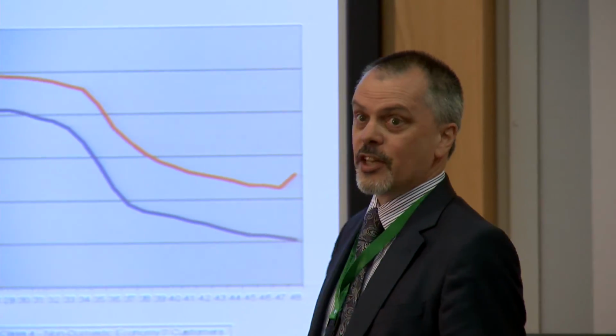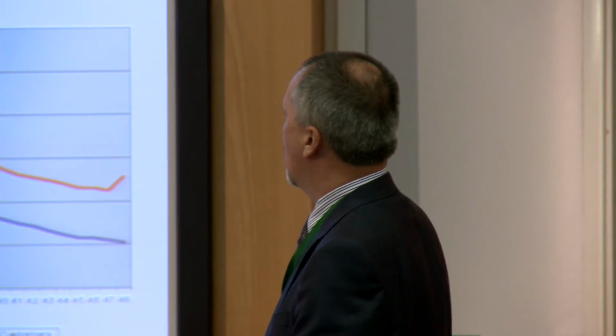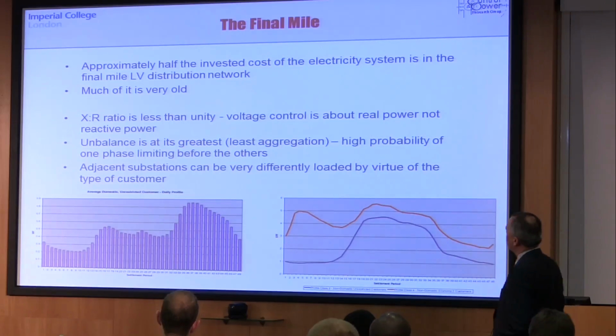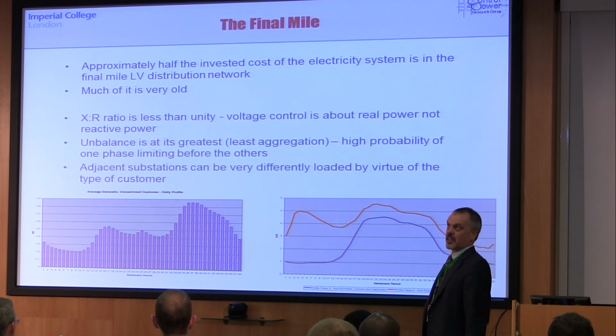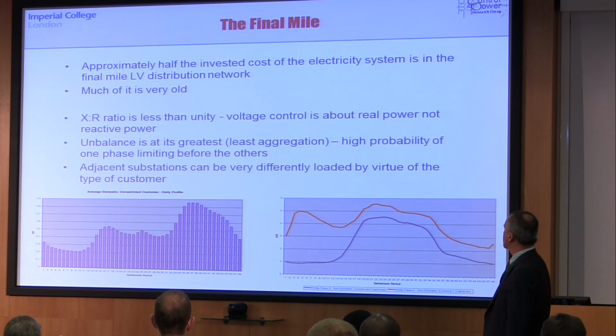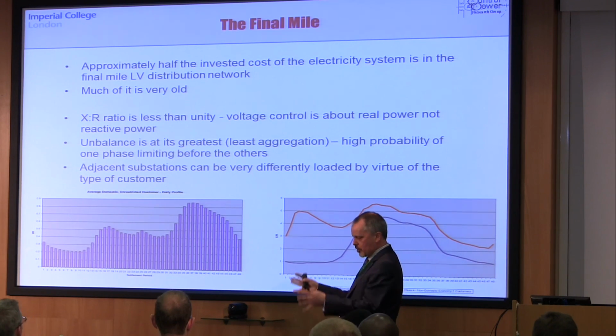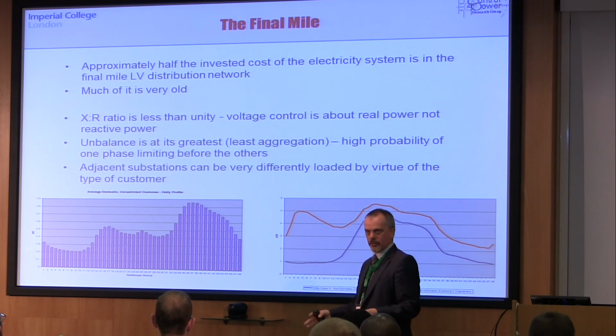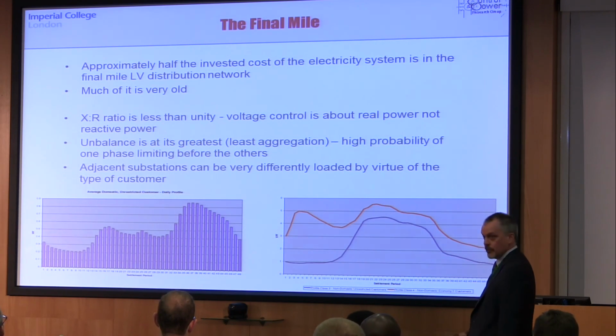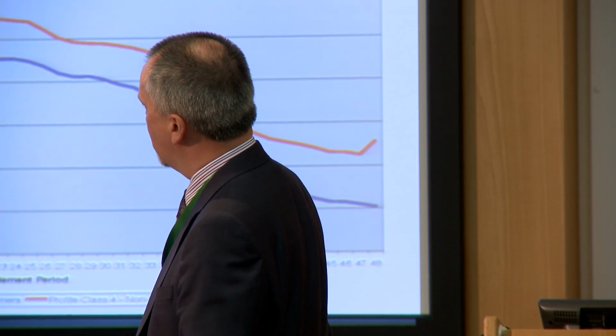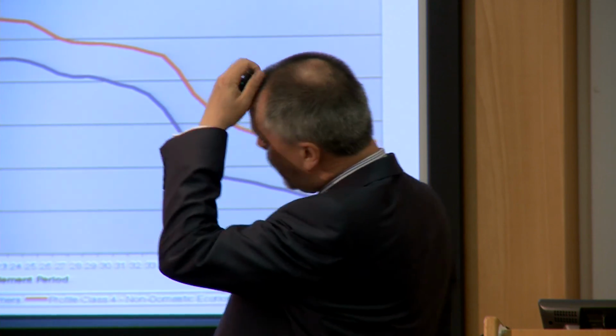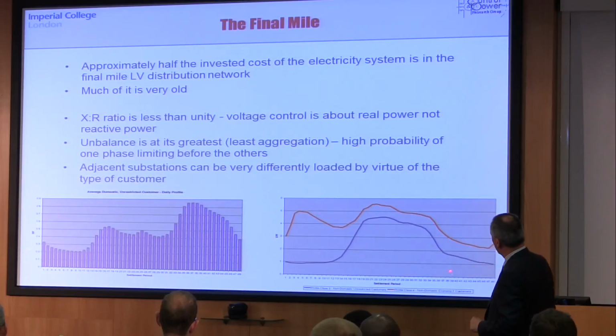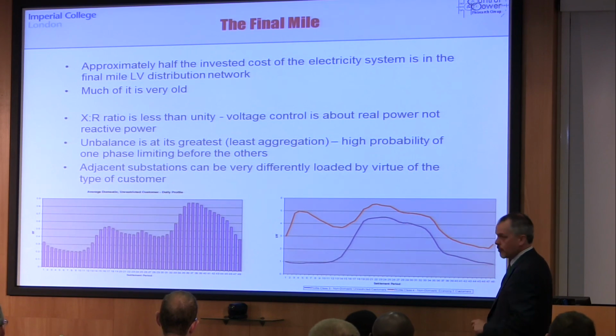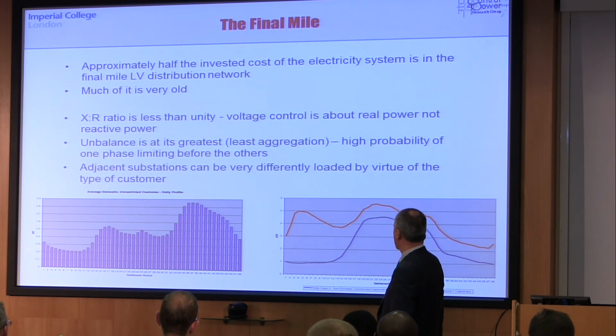Here, the X to R ratio is less than 1, so reactive power is doing very little for us in terms of voltage control, so we have to do real power manipulation. It's here that unbalance between the phases is at its greatest because we have the least aggregation of loads, so high probability that one phase is going to be problematic before the others. And because substations feed groups often of quite similar consumers, adjacent substations have different use patterns, and that's an opportunity. Some might follow a domestic use pattern with heavy demand in the early evening, relatively light in the midday section, whereas a commercial district, maybe next door, has heavy use in the middle of the day, unless it's incentivized with tariff structures to do some early hours of the morning consumption.